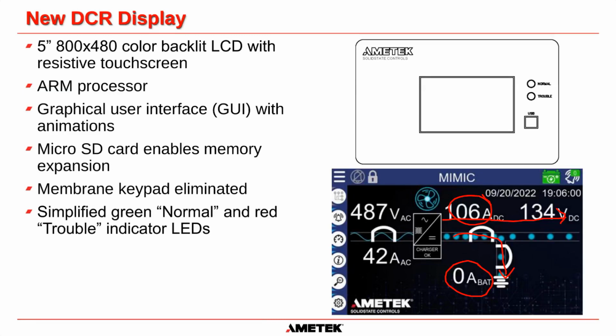Is it just to one decimal point, that current? It's not to any decimal points — it's a whole number, so it's always rounded down. So even if that was 0.9 amps, it's still going to show 0 amps. That's the same with most battery chargers, whether it's an analog meter or a digital meter. It's very difficult to monitor a small amount of DC current — it's just the nature of the beast, unfortunately. So there are some resolution issues, but that's the same with everyone.